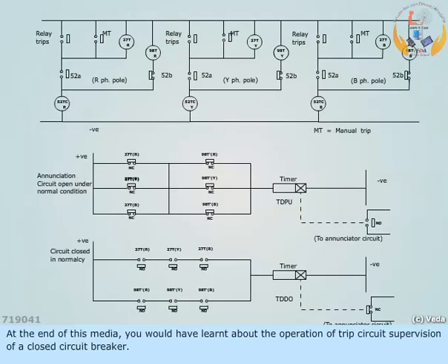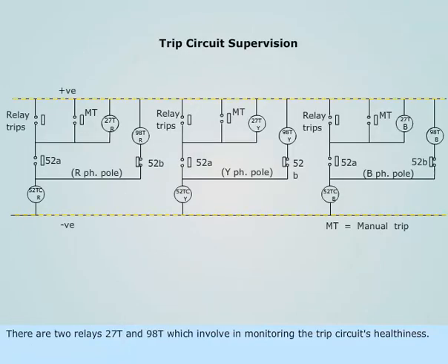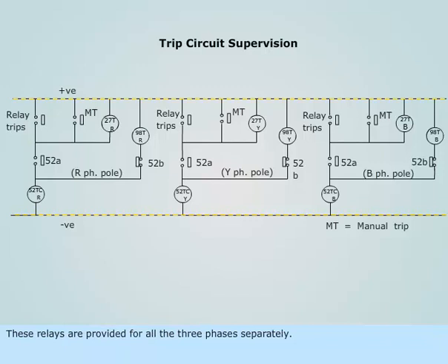At the end of this media, you would have learnt about the operation of trip circuit supervision of a closed circuit breaker. There are two relays, 27T and 98T, which are involved in monitoring the trip circuit's healthiness. These relays are provided for all three phases separately.